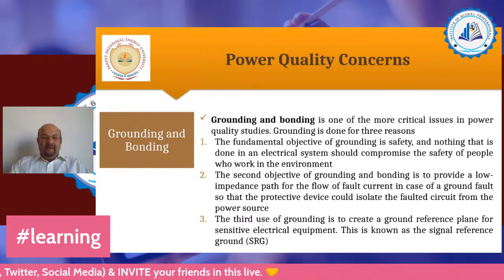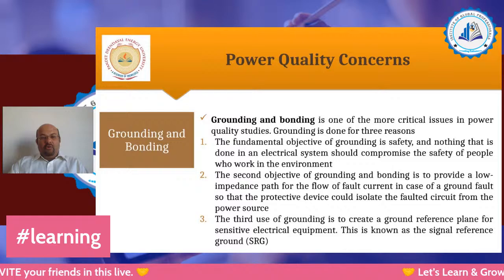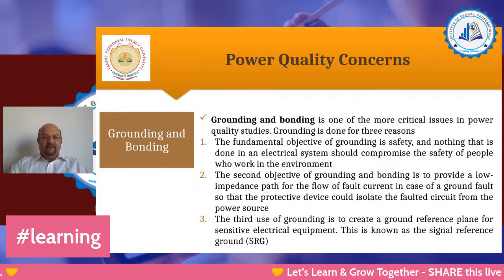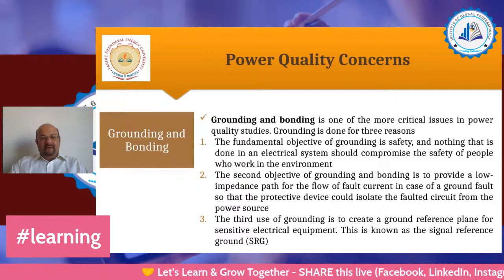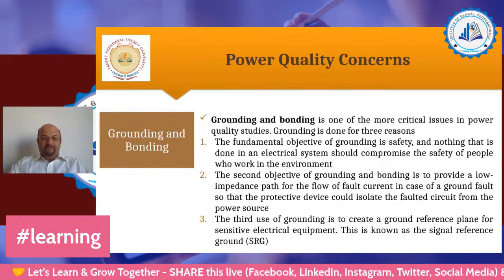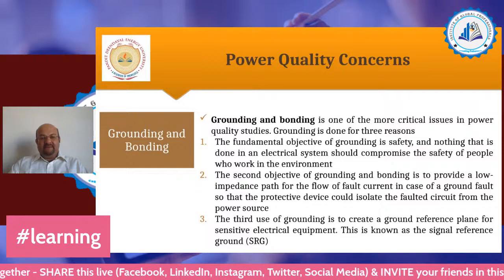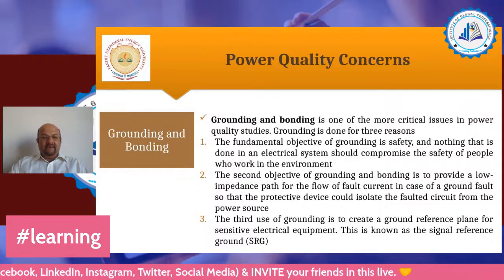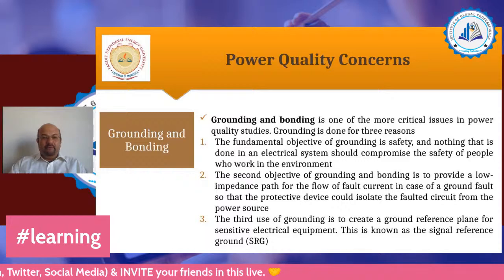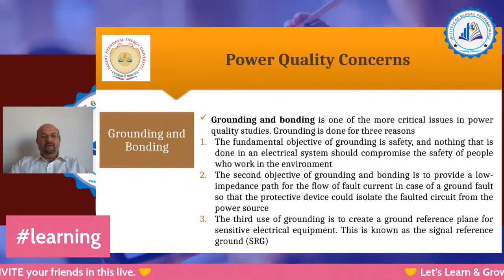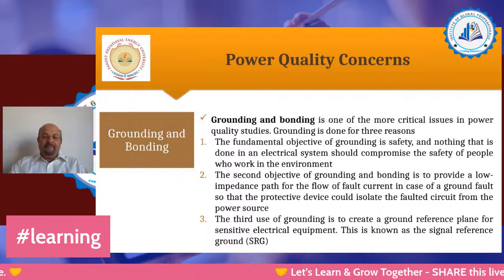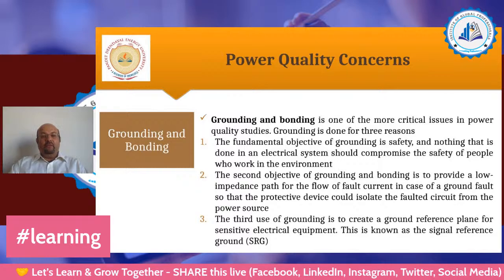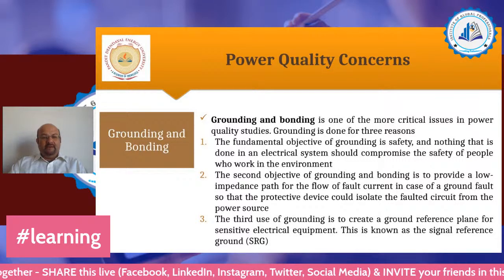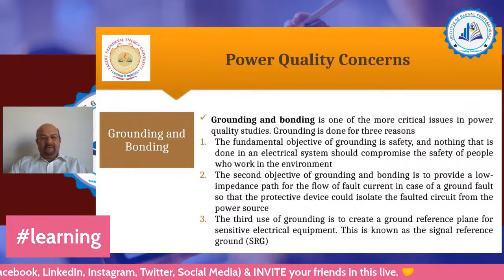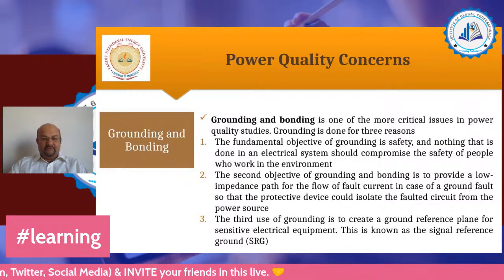The next concern is grounding and bonding. Grounding and bonding is one of the more critical issues in power quality studies. Grounding is done for three reasons. The fundamental objective of grounding is safety, and nothing that is done in an electrical system should compromise the safety of people, that is, personnel working in the environment. The second objective of grounding and bonding is to provide a low impedance path for the flow of fault current in case of a ground fault, so that the protective device can isolate the faulted circuit from the power source.